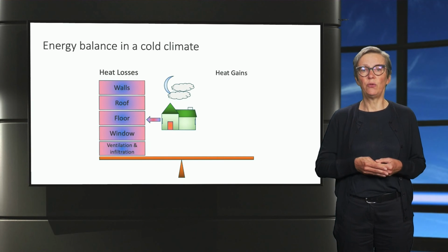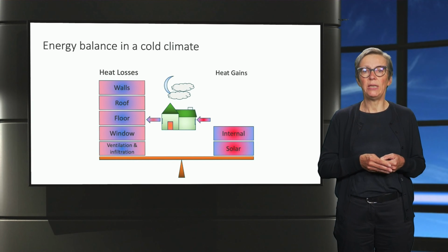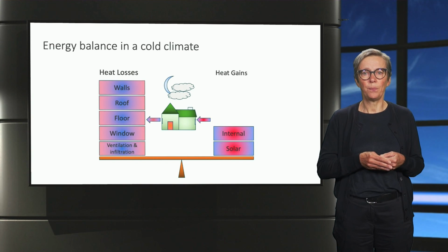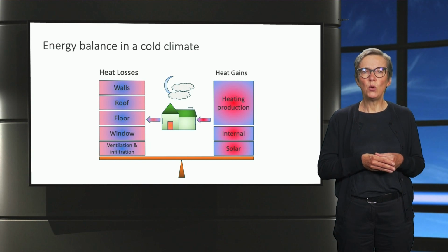On the other side of the balance, we listed the heating gains, which include solar gains and the internal heat gains. What you can observe is that for a poorly insulated residential building to be comfortable, a substantial amount of heat needs to be produced. Please note that this picture can look quite different when you investigate a well-insulated building.